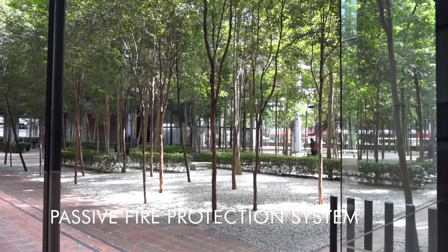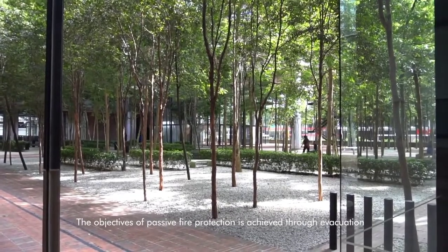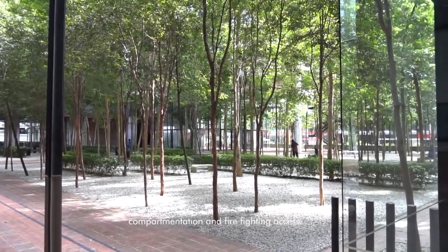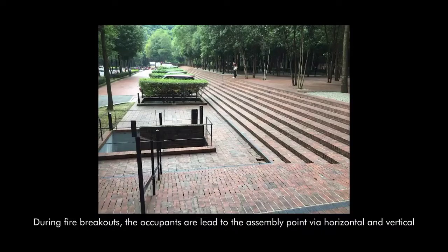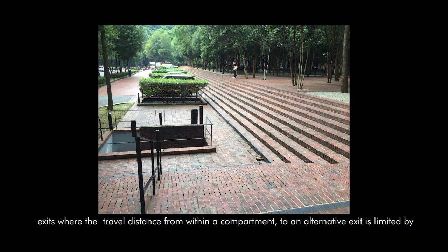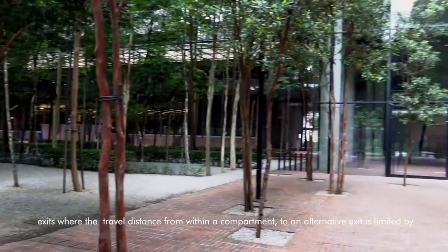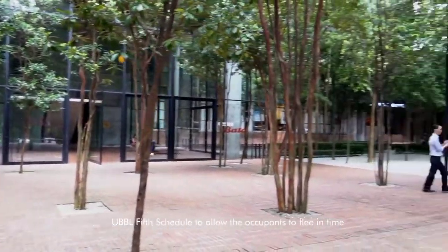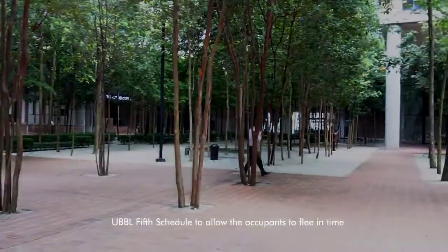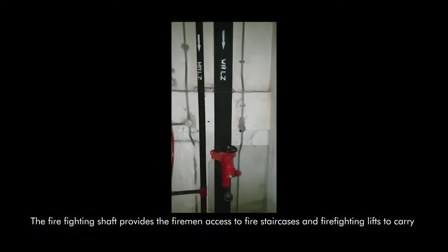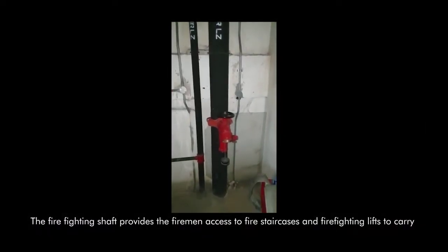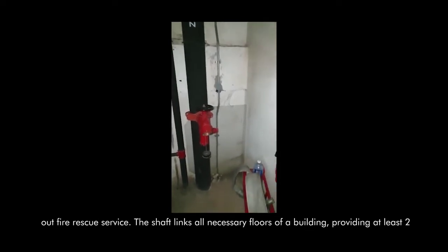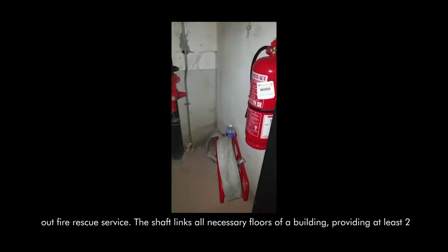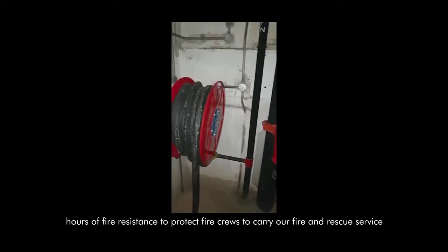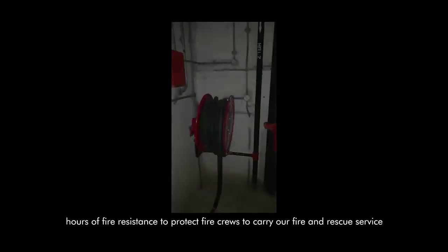Passive fire protection system. The objective of passive fire protection is achieved through evacuation, compartmentation, and firefighting access. During fire breakouts, the occupants are led to the assembly point via horizontal and vertical exits where the travel distance from within a compartment to an alternative exit is limited by UBBL 5th Schedule to allow the occupants to flee in time. The firefighting shaft provides the firemen access to fire staircases and firefighting lifts to carry out fire rescue service. The shaft links all necessary floors of a building, providing at least 2 hours of fire resistance to protect fire crews to carry out fire and rescue service.